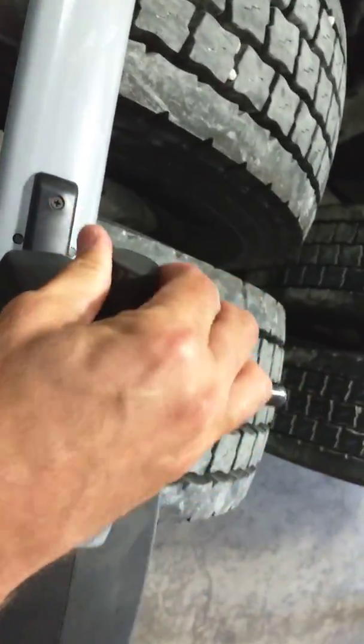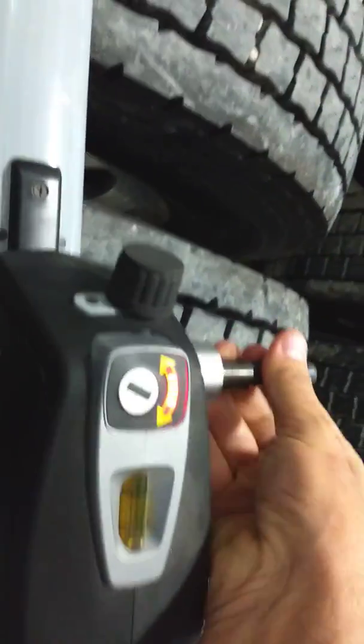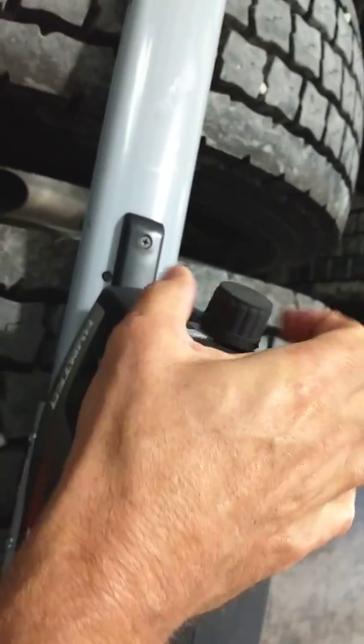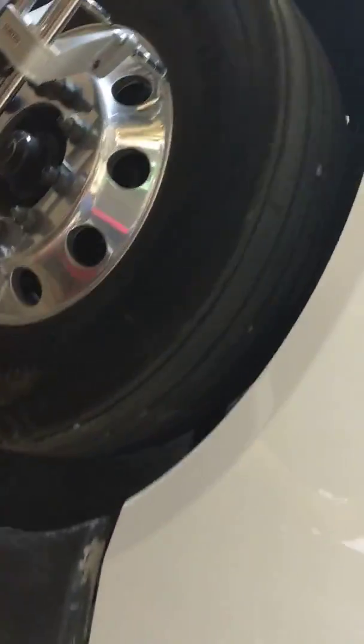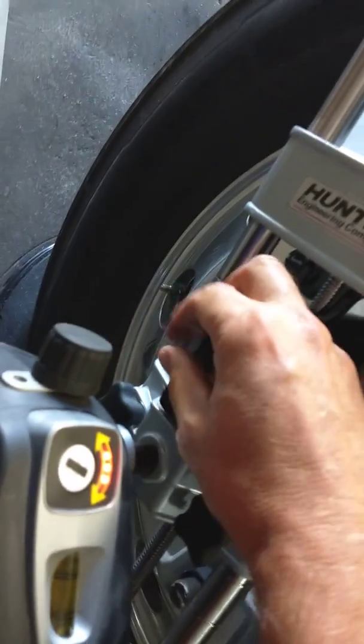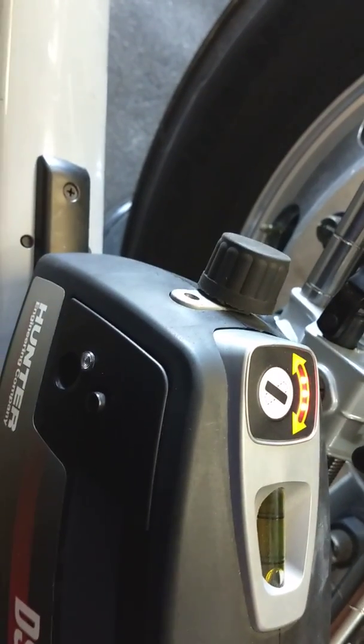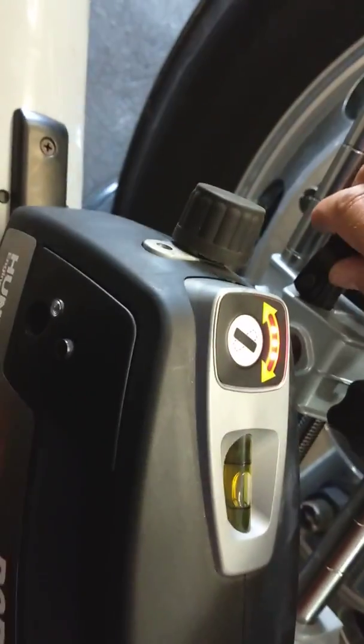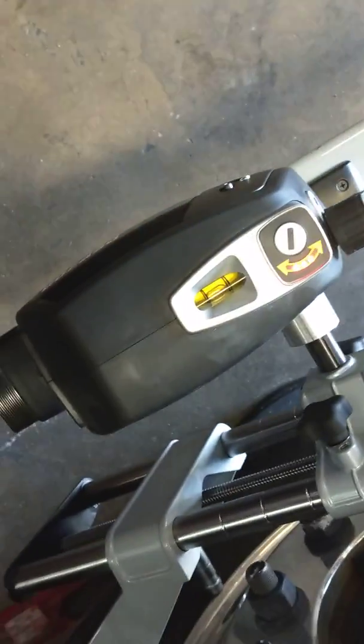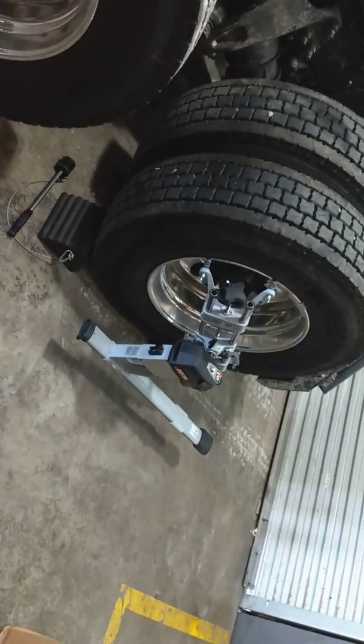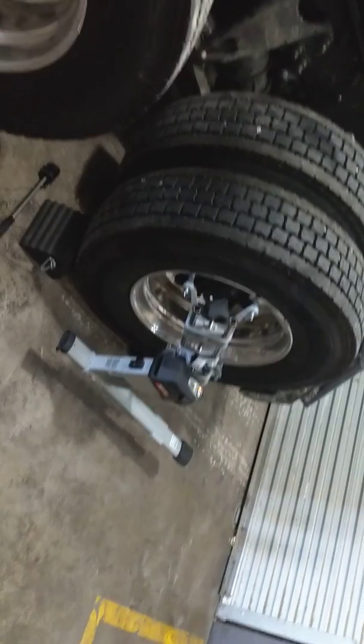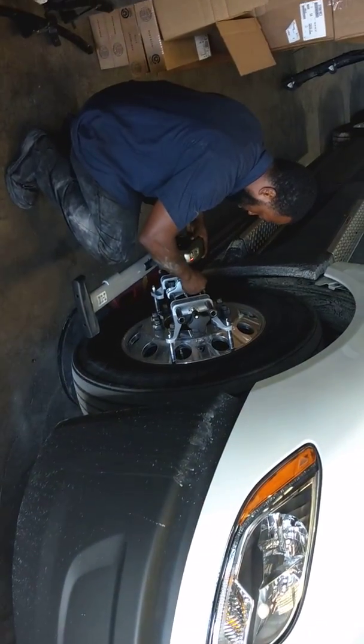So we're going to move these all around, and don't forget, when you take this rear sensor, that you want to roll that notch to 12 o'clock, tighten it back down real good, and then you're going to level it with a butterfly when you reinstall this. Go ahead and move the other one. So I brought the left front up. My knob is locked. I'm going to level it, and lock it down, get it nice and level. So Sean is moving the other two sensors, so now the right front has moved to the left rear, and now the left rear is on the right front.